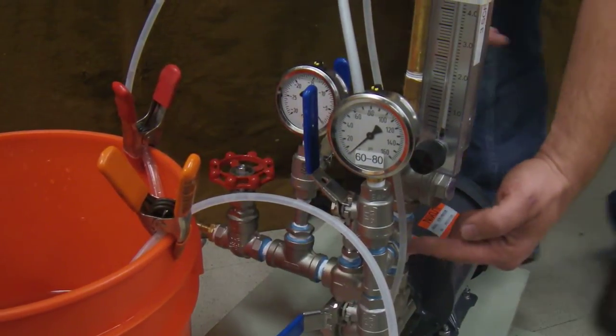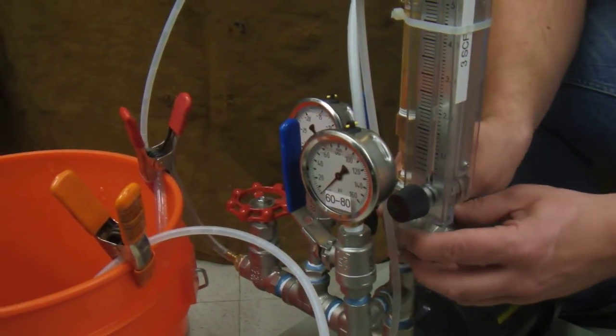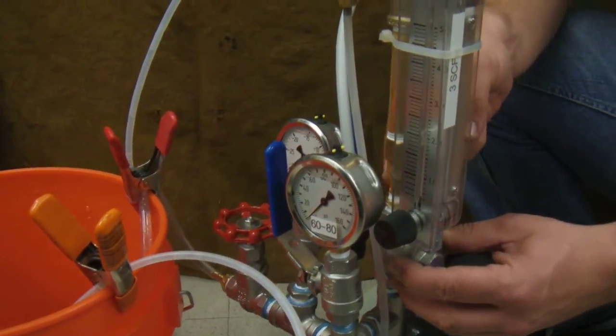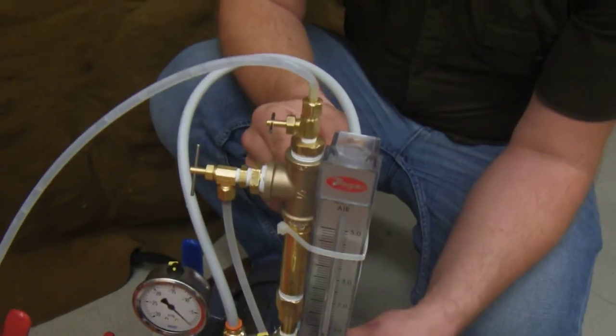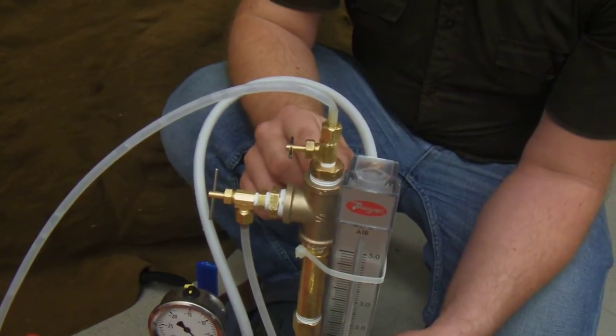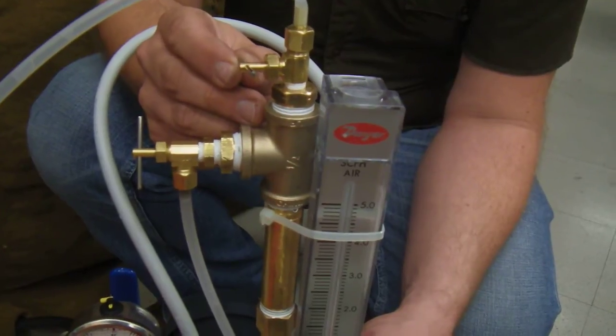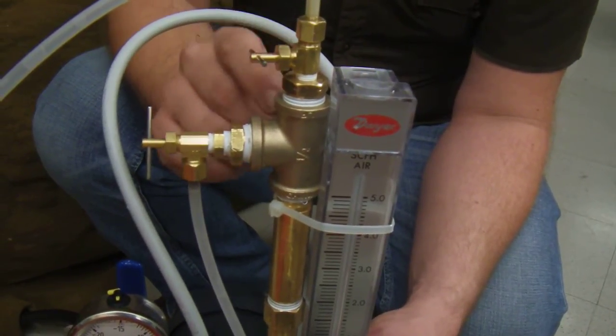Then the fluid goes up from the outlet through this check valve right here and into the column, the separation column. So the microbubble air solution passes up through here. Any extra air that's in solution will rise to the top. And this is a bleed valve that's left open just a tiny bit to let any air that shows up in this pocket at the top leak out and go back into the bucket.